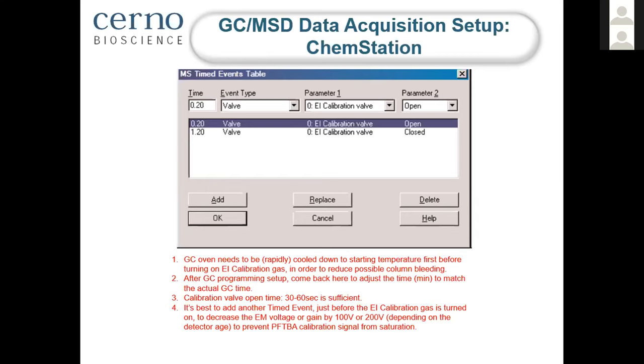You can cool down it rapidly at the end of the run to the initial temperature, to the starting temperature before the temperature ramping. The idea is to reduce the column bleeding at high temperature so that it does not interfere with the EI calibration gas or CI calibration gas if you're running the CI mode. So to reduce the interference, we like you to cool down the oven. So that's another time event that you might want to program into the GC.